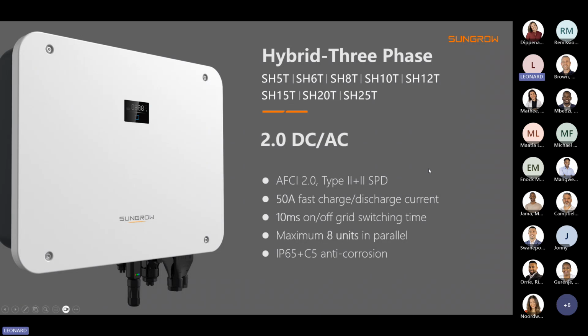Just in terms of protection, we have arc-fault circuit interruption 2.0 built into all these inverters with SPD type 1 and 2 protection. It has 50 amp fast charging current on the battery side with a 10 milliseconds seamless switching, and you can maximum parallel 8 units of these solutions in parallel. We also have an IP65 C5 anti-corrosion protection, which is aluminium enclosed, so you can use this as a coastal solution.